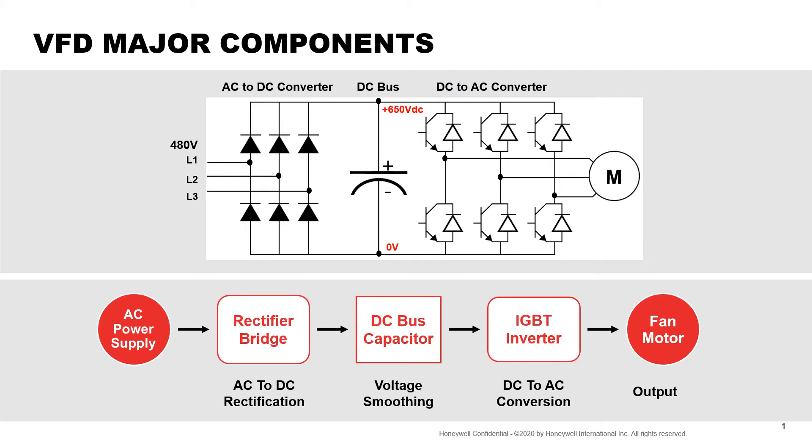VFDs have three subsystems: a rectifier, the DC bus, and the inverter. Supply power is usually three-phase, and the first component is the rectifier that converts the AC to DC. Next, the power goes to the capacitors in the DC bus. These smooth out ripples in the DC current. Lastly, transistors called IGBTs convert it back to AC, but in a way that allows us to choose a frequency. AC induction motors rotate at a speed that is proportional to the frequency of the electricity powering them. So when a VFD varies its frequency, it varies the speed of the motor. This allows us to drive the motor at different speeds.